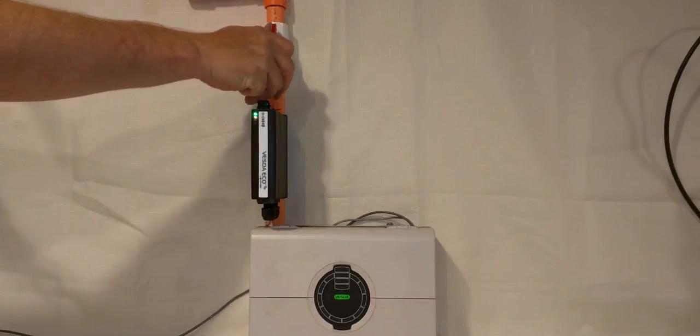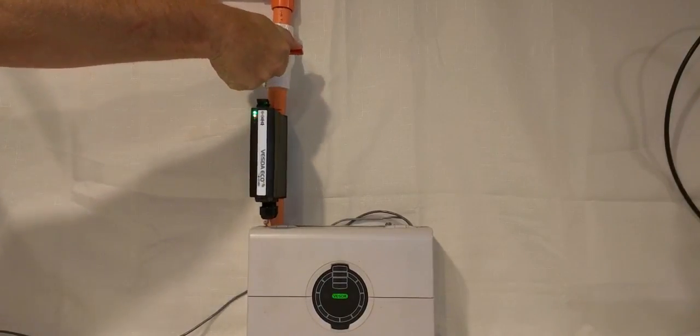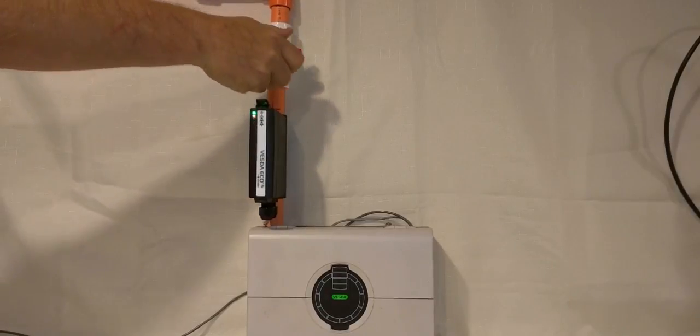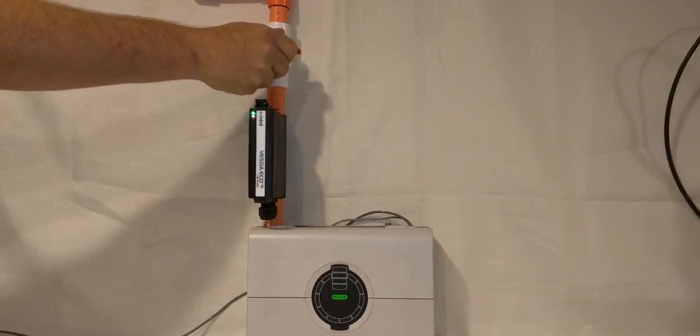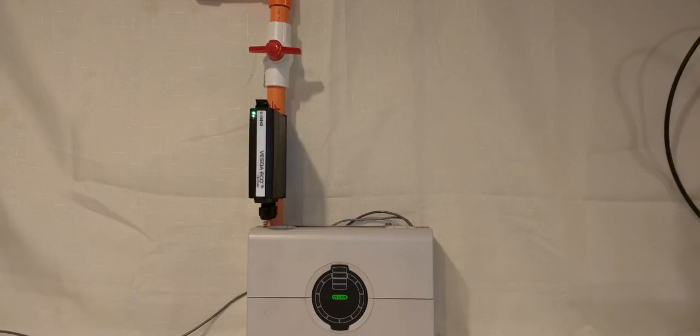Next, close the ball valve above the ECO. If there is no ball valve, you must install one. This prevents external air from diluting the calibration gas.